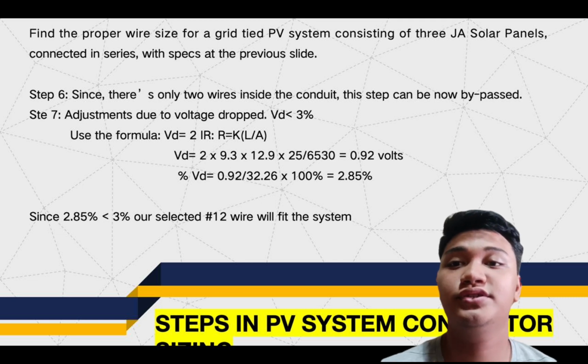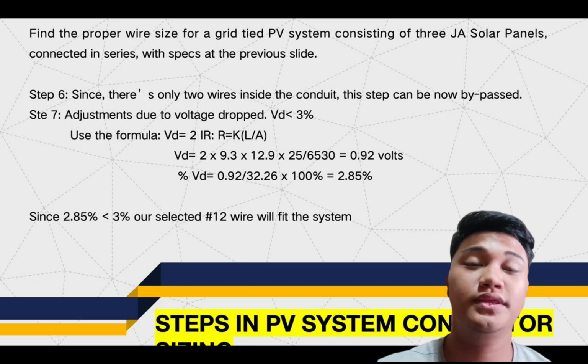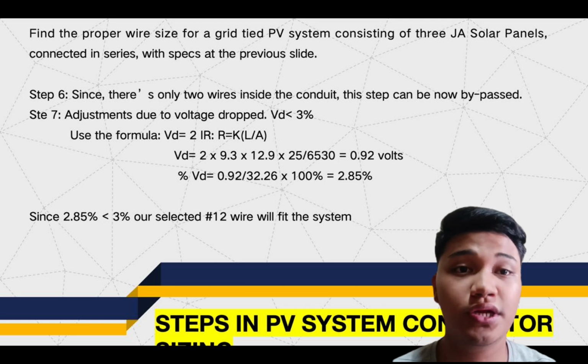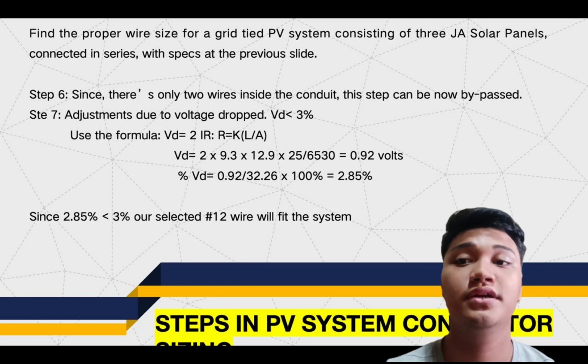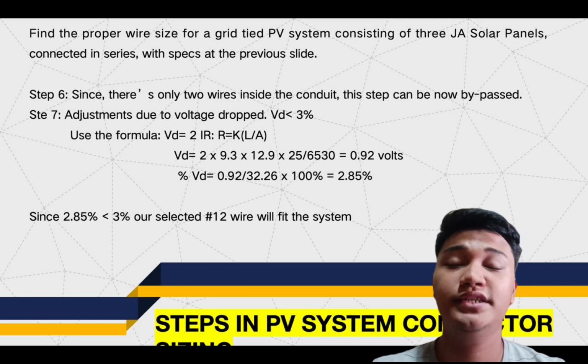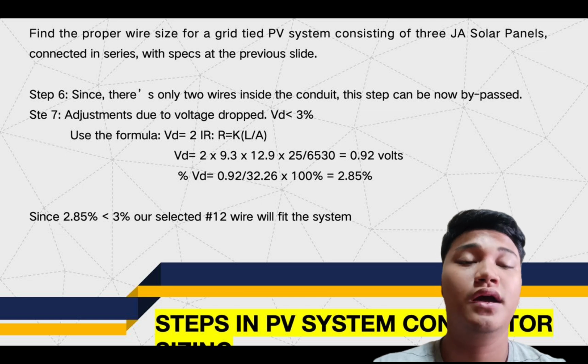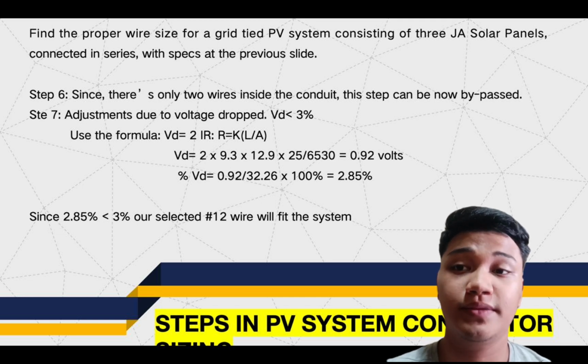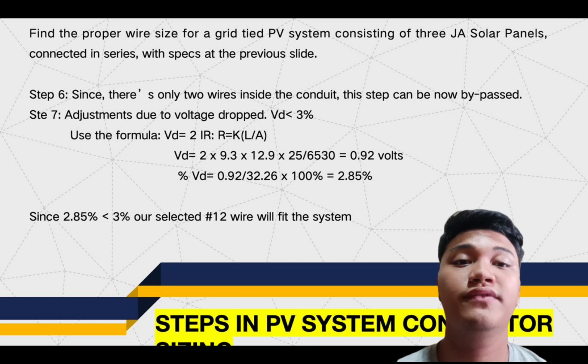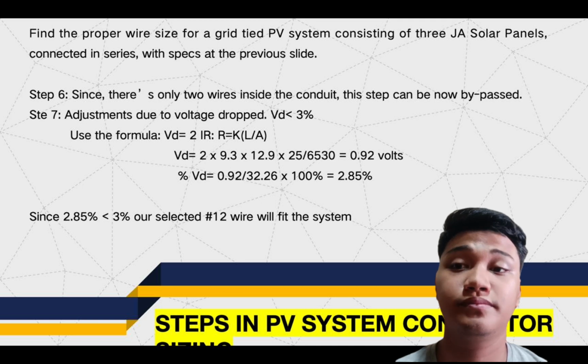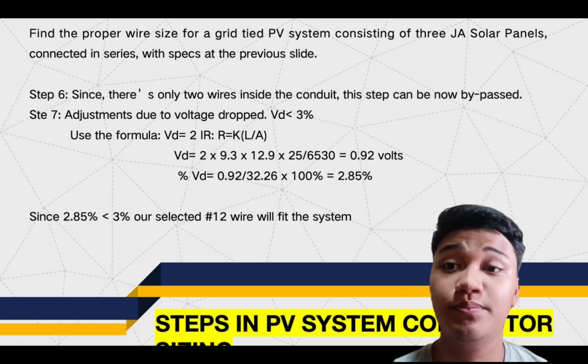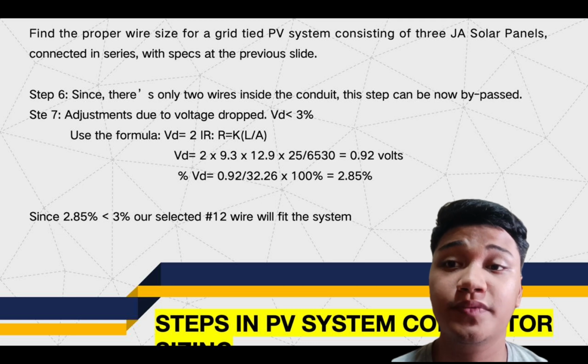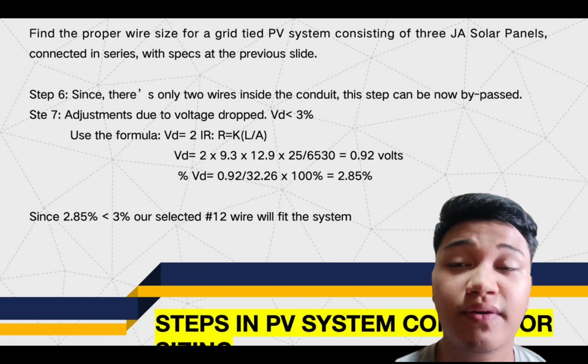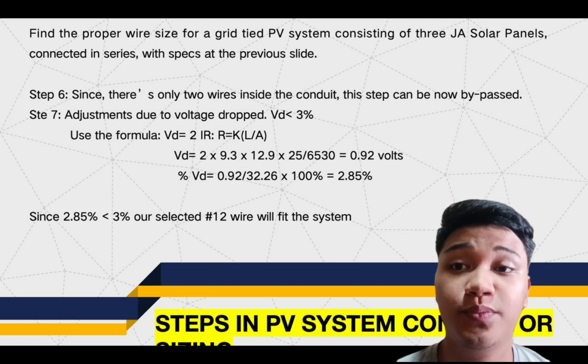Step 6. Since there's only 2 wires inside the conduit, this step can now be bypassed. Pwede na po natin i-bypass yung step number 6. Step number 7, adjustment due to voltage drop. Ang voltage drop natin is 3%. Gagamitin lang natin yung formula na VD is equals to 2IR. And making VD is equals to 2 times 9.3 times 12.9 times 25 over 6,530 is equals to 0.92 volts.